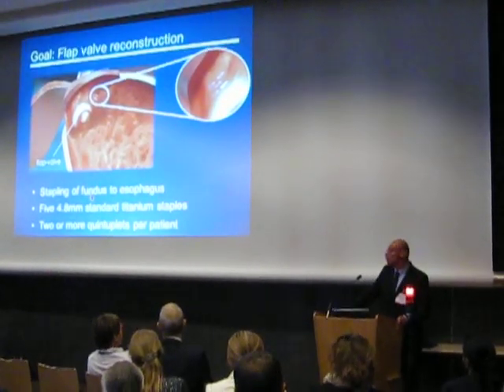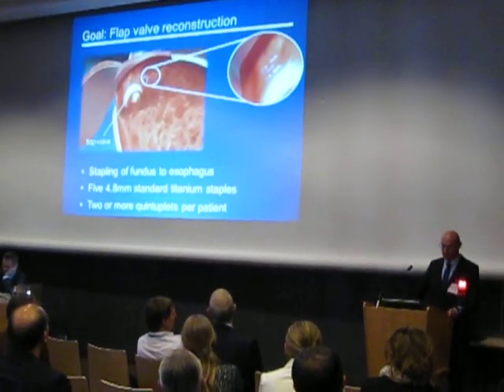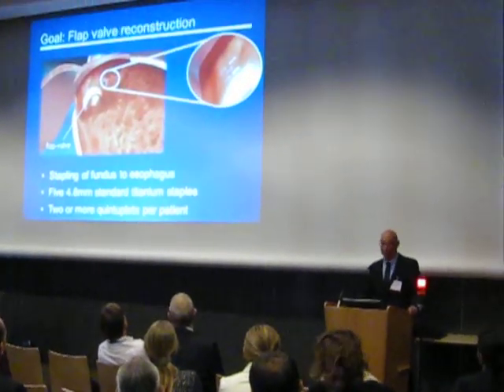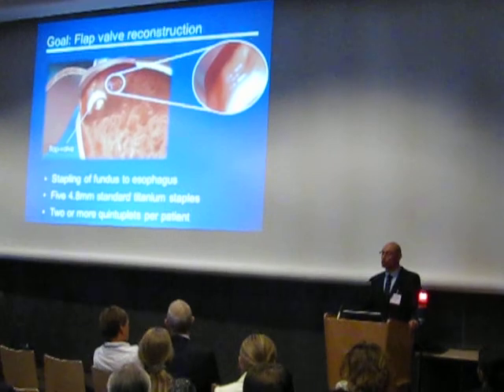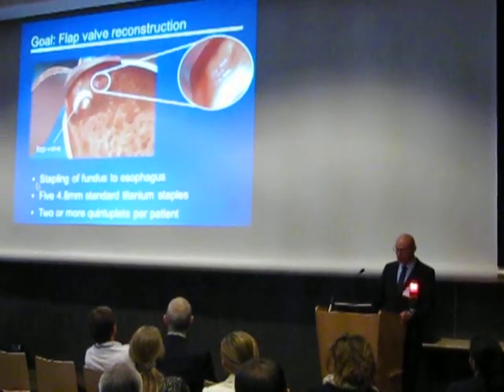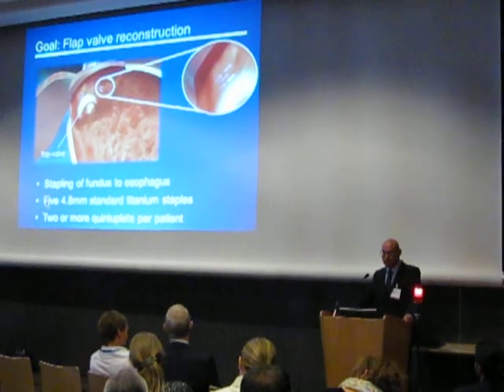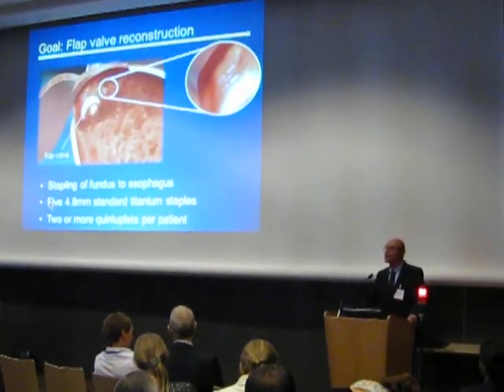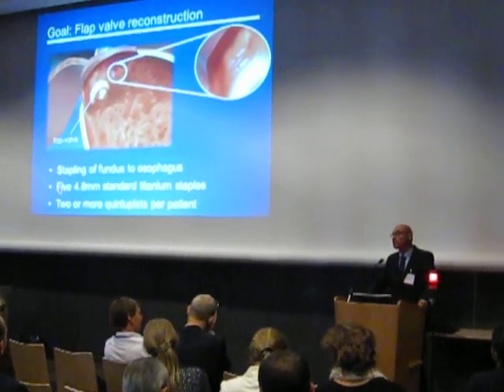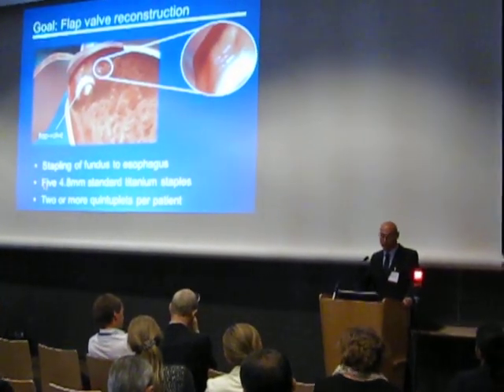We achieved our goal: we are stapling simultaneously five staples, and after stapling the device will go back below and insert again — the procedure repeats two or more times per patient. The staples we are using are 4.8mm titanium staples. These are staples that are used in green staples or sutures, and have been used for six decades in gastroesophageal anastomosis. They have proven their durability.